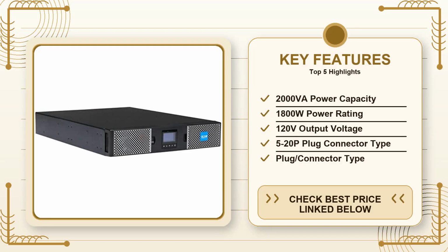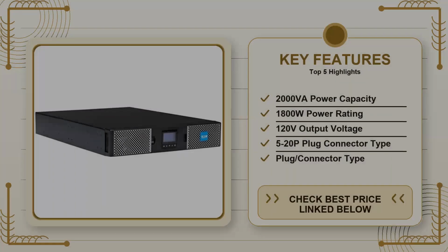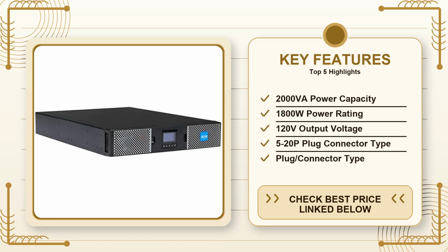One thing that trips up many buyers is the runtime you actually get on battery. The 9PX is rated at 2000VA, but you need to consider the load you plan to put on it. If you're feeding a 200-watt desktop, a couple of monitors, and maybe a router, you're well under half the unit's capacity. In that scenario, I saw runtime figures of roughly 15 minutes before the battery depleted, which gives enough time to save work and shut down safely.